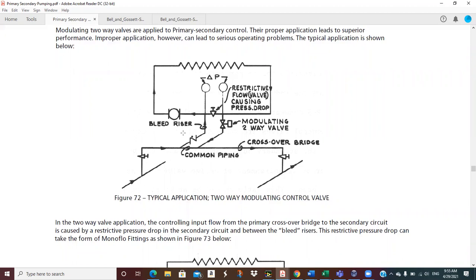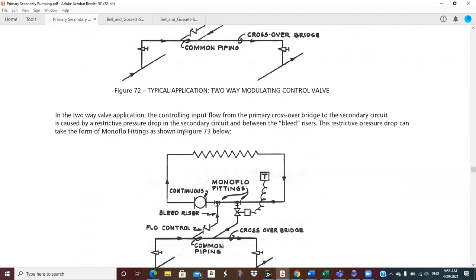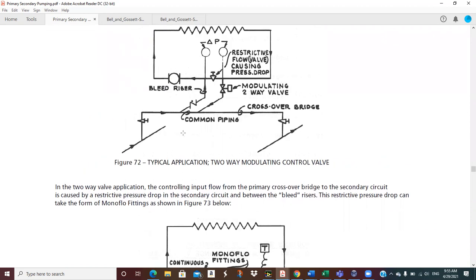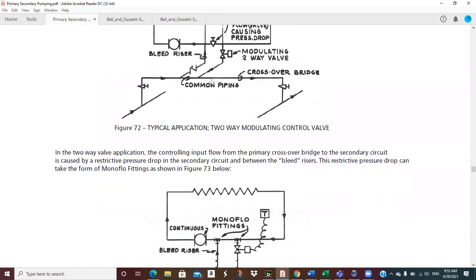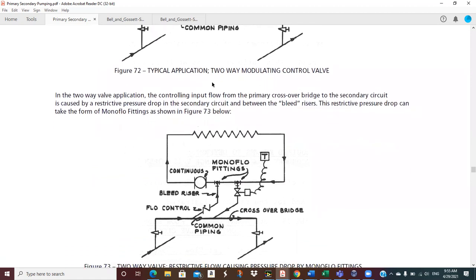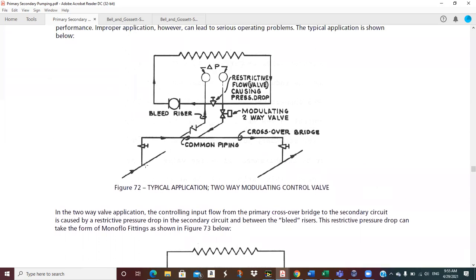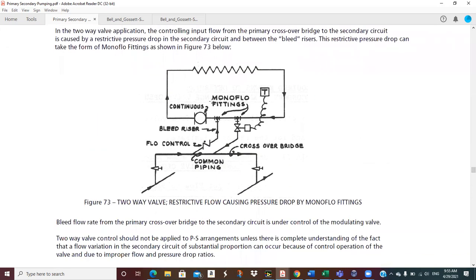Let's see. Typical application, two-way. In the two-way valve application, the controlling input flow from the primary crossover bridge to the secondary circuit is caused by the restrictive pressure drop in the secondary circuit between the bleed risers, and that's caused by that balancing valve right there. But of course, now Bell and Gossett, they have their special Monoflo fittings that accomplish that for you. And they're more than happy to sell them to you because that's why they put all this stuff up there to help sell product. Okay, and so when they show these little diagrams like this with these Monoflo fittings, what you should think about is this situation here, because those fittings are establishing the pressure drop across that pipe. So think this when you see this, and you'll be right.